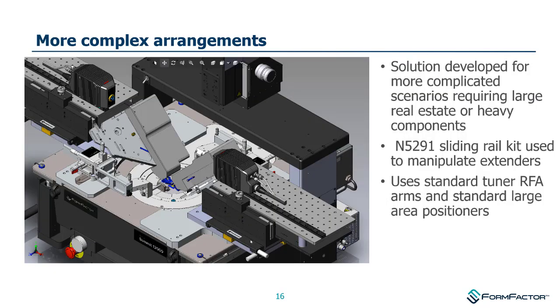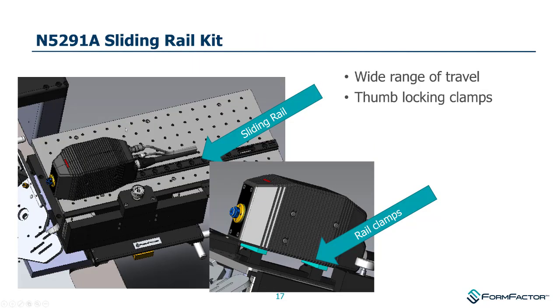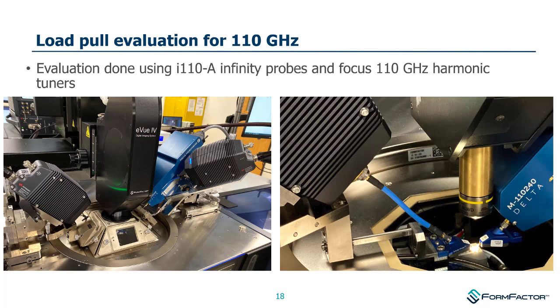Some customers need more complex arrangements where the real estate on our normal RF platform is not viewed as sufficient. For these cases we use large area positioners with conventional angled RFA arms as standard, and we have the ability to move the frequency extender on sliding rails, which aids the calibration process by allowing us to slide the extenders towards each other to get the cable ends close to one another.